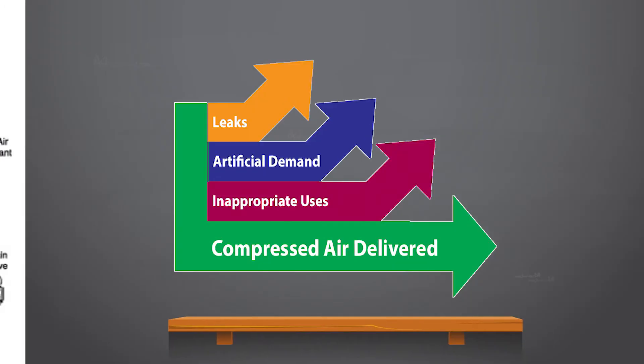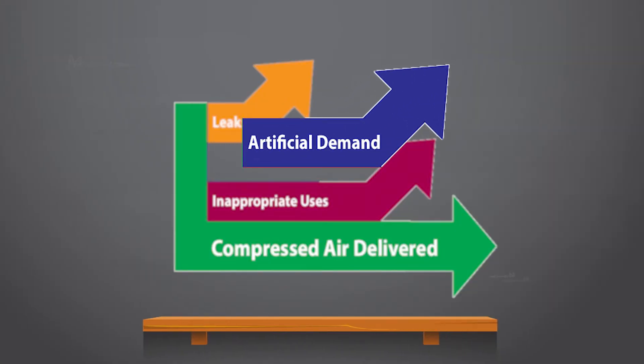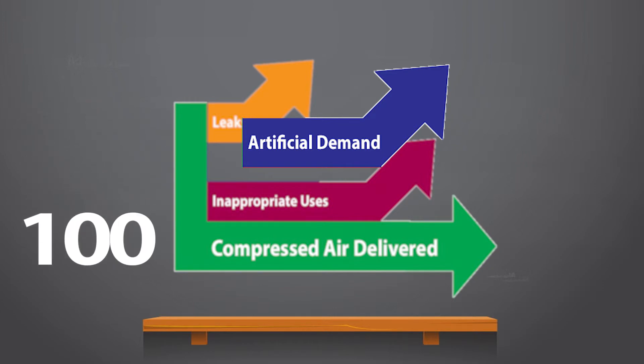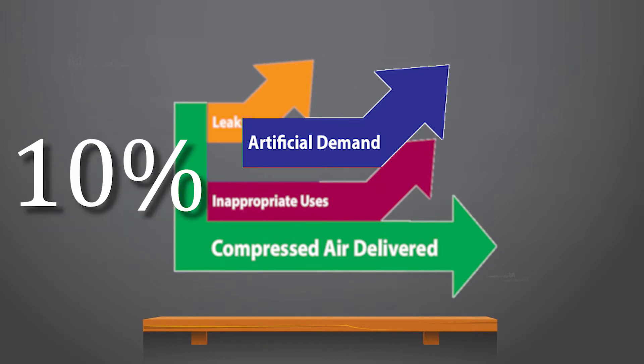Plants often run at a higher pressure than needed. If you lower pressure, compressor power is reduced and unregulated uses consume less air. For example, lowering pressure from 120 psi to 100 psi saves 10% power at the compressor and less air is used.